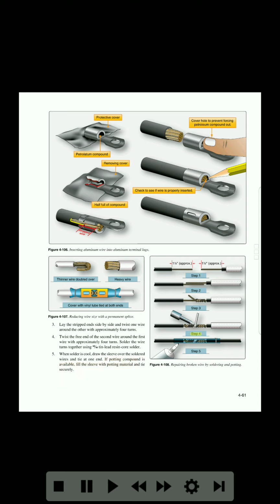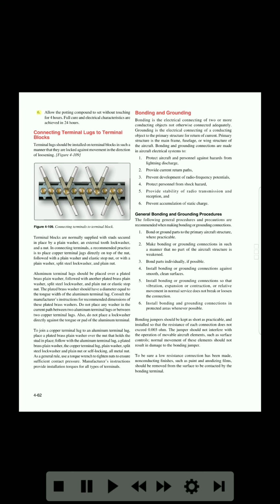Step 4. Step 5. Figure 4-108. Repairing broken wire by soldering and potting. 4-61. 6. Allow the potting compound to set without touching for 4 hours. Full cure and electrical characteristics are achieved in 24 hours. Connecting terminal lugs to terminal blocks.